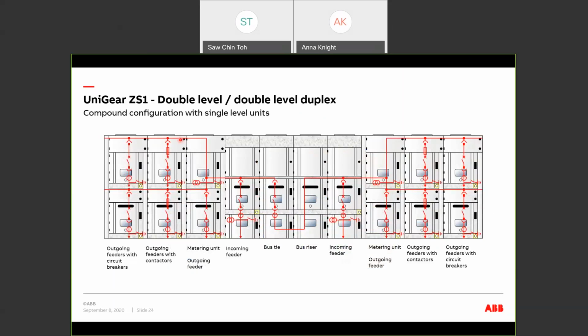This is a typical product panel lineup. We can actually mix and match the different types of switchgear in one lineup. For example, in this case, we have single level panels with a higher current, like 2000 amps coming in, and then they will distribute to the double level panel feeders with, for example, 1250 amps. So no transition panels are required. And as you can see, by using double level panels, we can reduce the feeder dimension by half.